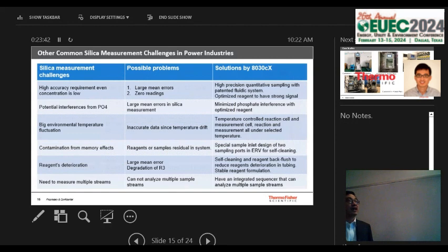Further, accuracy, right? We achieve accuracy through design, the way of quantifying the volume of intake using the liquid sensor and its fixed segment of the tubing. This way we achieved 0.1% volume quantification accuracy. And we also optimized the reagent so that it has a higher signal.